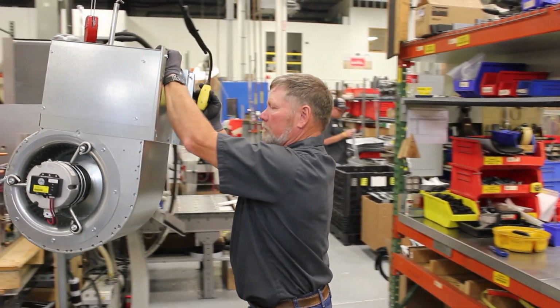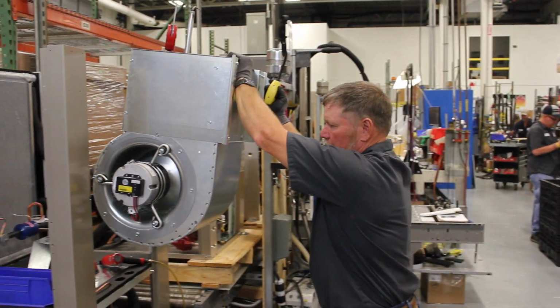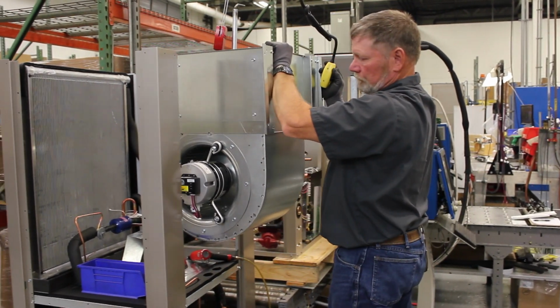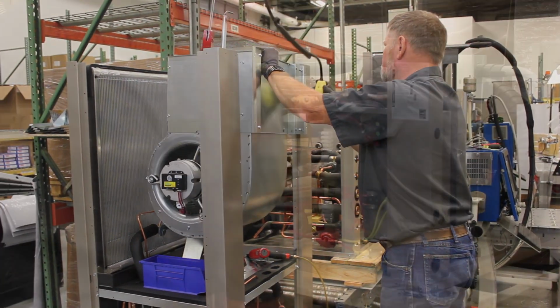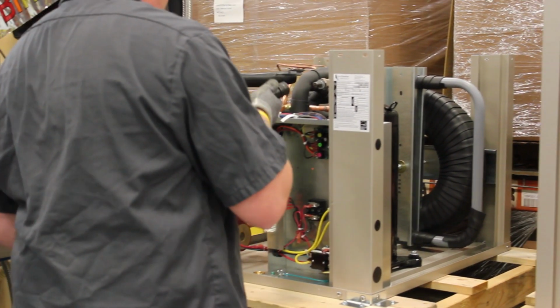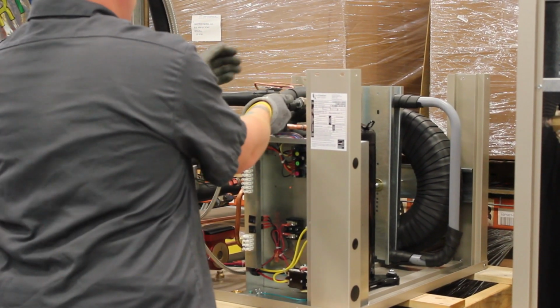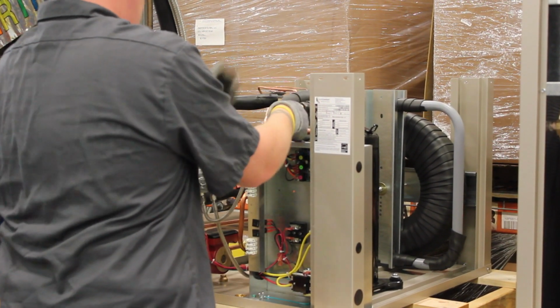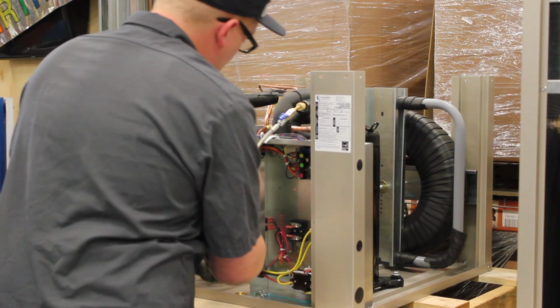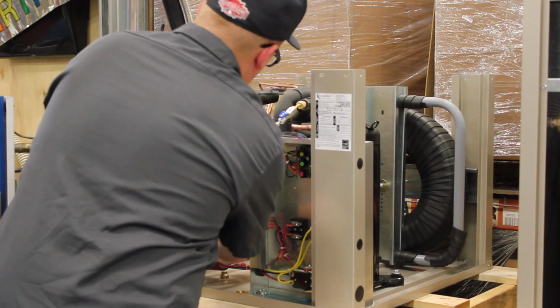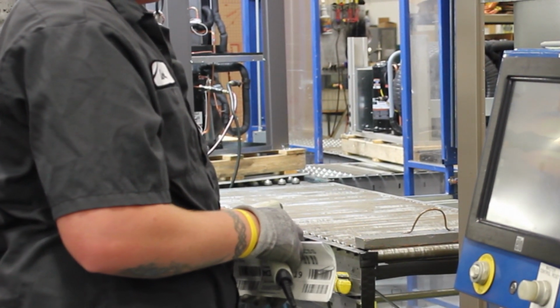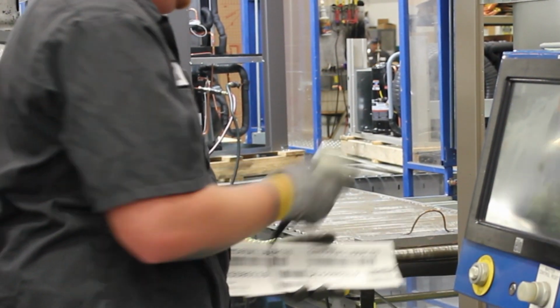Once leak detection is complete, the blower motor is assembled and installed. Then the unit moves on to the evacuation and charge station. The unit gets hooked up to the process charging tubes, vacuumed twice, and then we add in the refrigerant charge based on model and serial number. The refrigerant charge is computer controlled and is pulled directly from the bill of materials. This eliminates the possibility of the operator selecting the wrong charge amount.